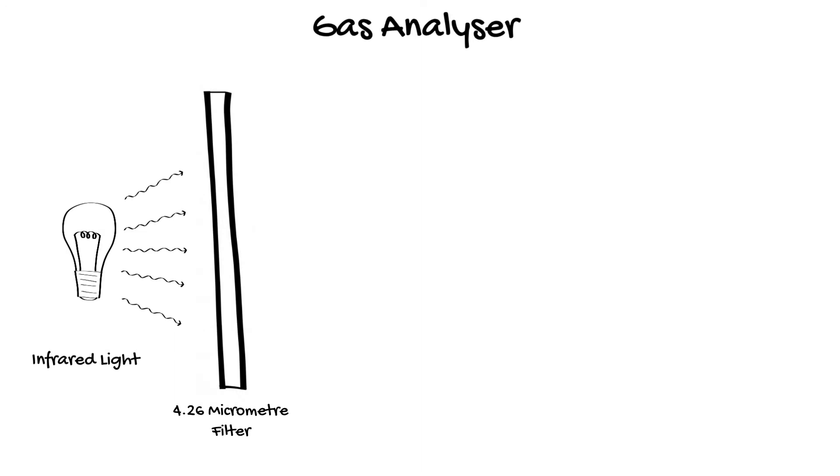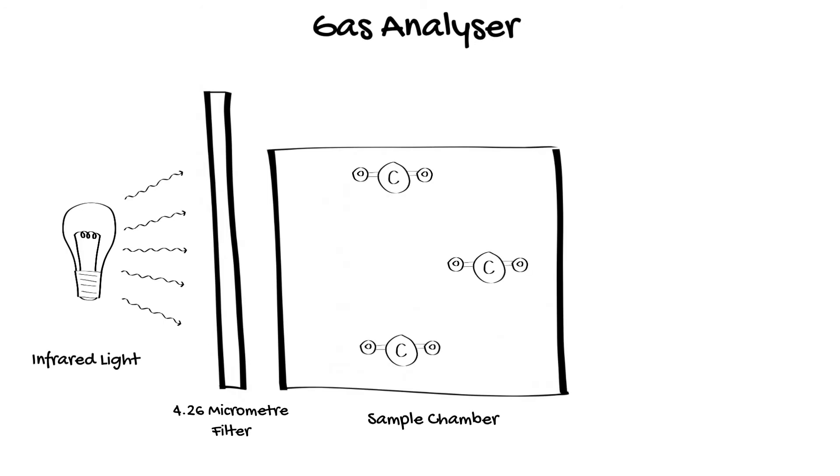The analyser consists of an infrared light source with the waves passing through a filter to allow the passage of only 4.26 micrometre wavelength light. This then passes through the sample chamber of expired gas with absorption of the 4.26 micrometre light being proportional to the concentration of carbon dioxide in accordance with Beer's law which we've discussed in the previous pulse oximetry video. Of note, the sampling chamber cannot be made of glass as this absorbs infrared light so a sapphire crystal window is used in the sample chamber.